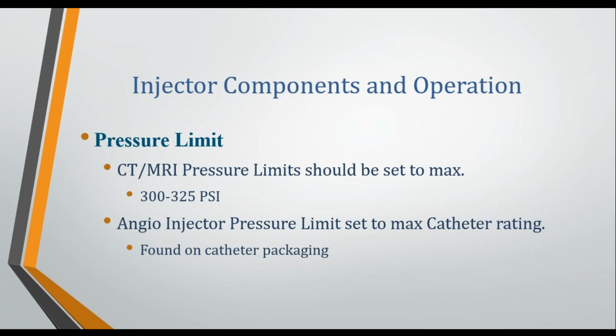One last thing on pressure limiting. Again, this kind of harkens back to you've seen them all, but there are subtle differences between each injector type and injector model, small differences, and this is one of them. For CT and MRI systems, the pressure limit should be set to max. As high as the CT injector or the MRI injector can go, that's what it should be set to. As a matter of fact, Medrad's MRI injector, the Spectris Solaris, the operator can't select pressure limits. It's factory set at 300 psi. It's not even a selectable option to the operator.